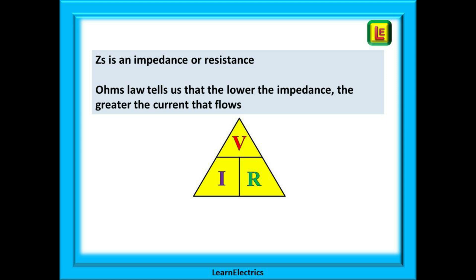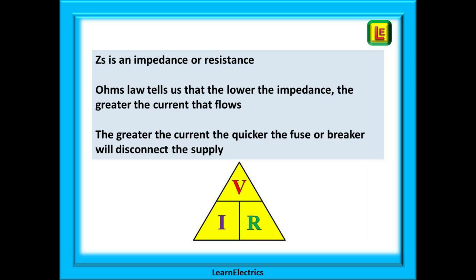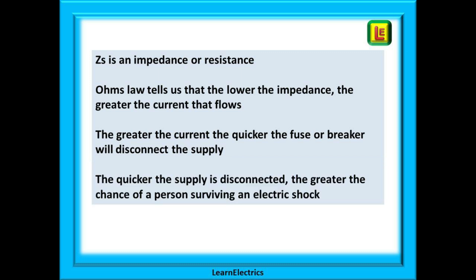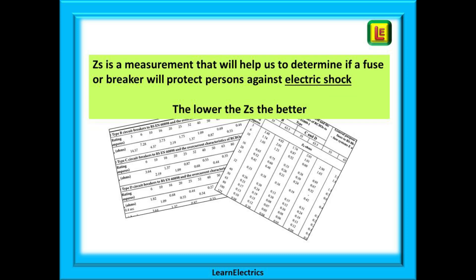Ohm's law tells us that the lower the impedance, the greater the current that flows. The greater the current that flows, the quicker the fuse or breaker will disconnect the supply. The quicker the supply is disconnected, the greater the chance of a person surviving an electric shock — and we want big currents to flow during the fault. ZS is a measurement that will help us determine if a fuse or breaker will protect persons against the dangers of an electric shock during a fault. The lower the ZS the better, because this means bigger fault currents.